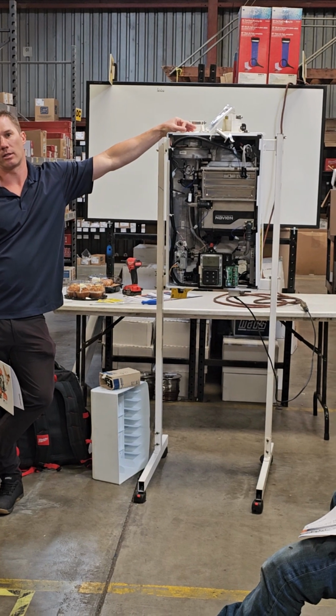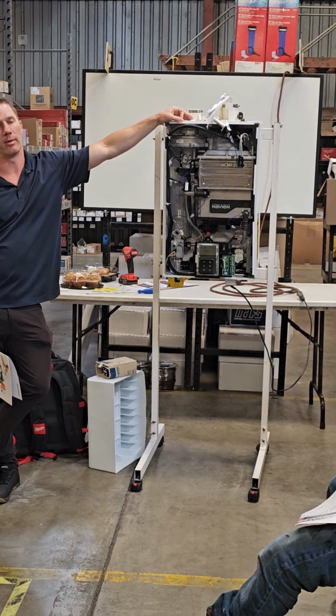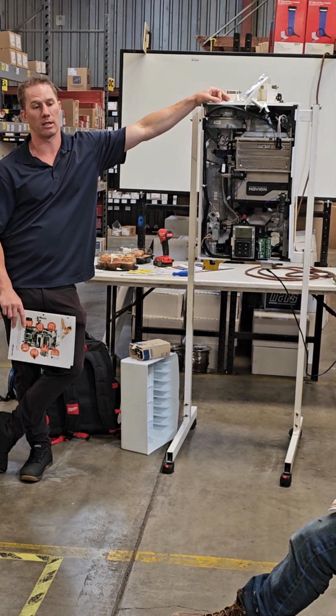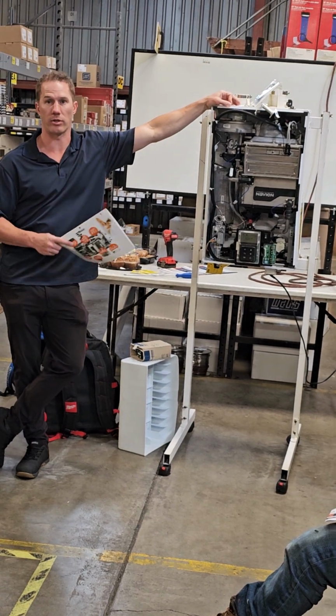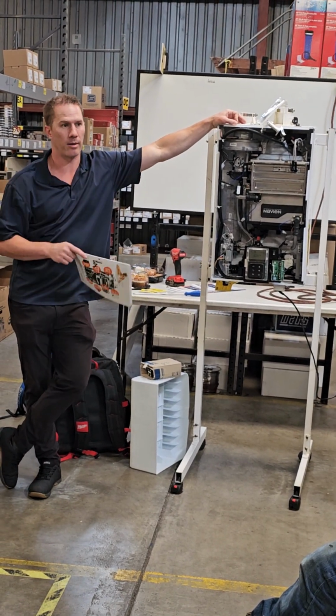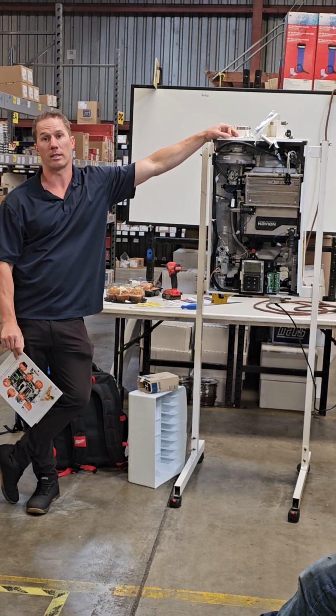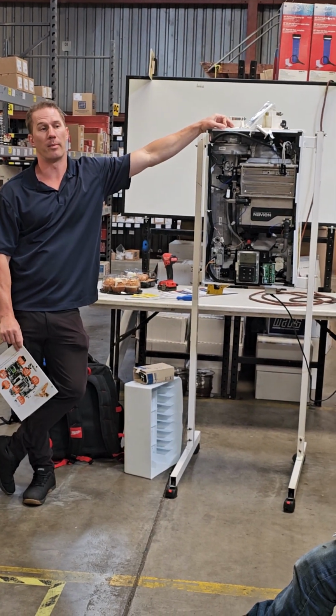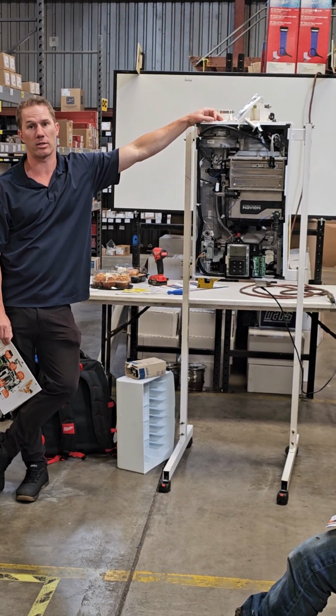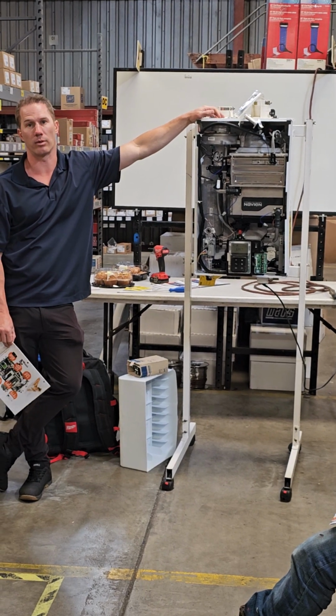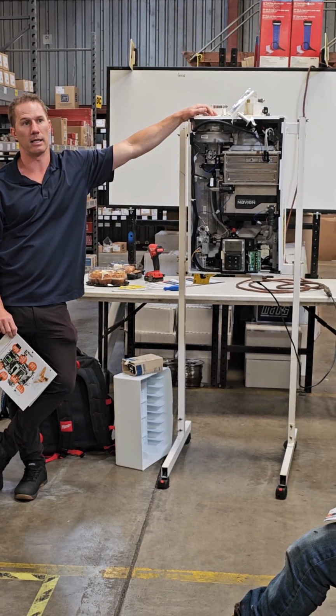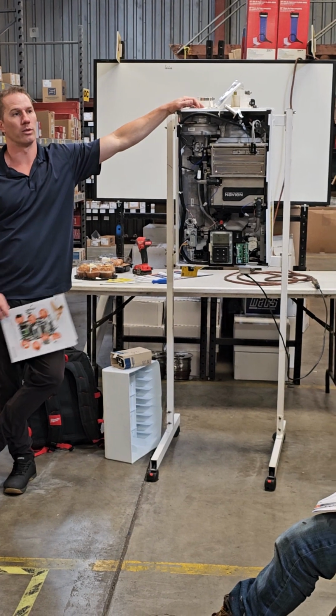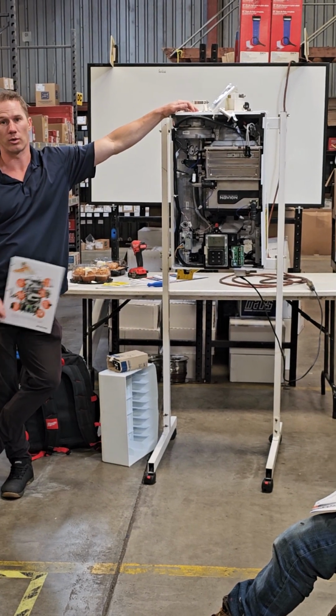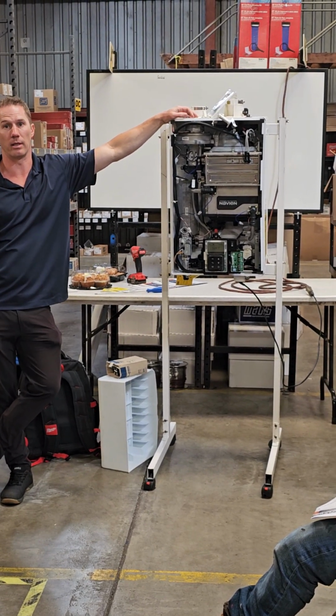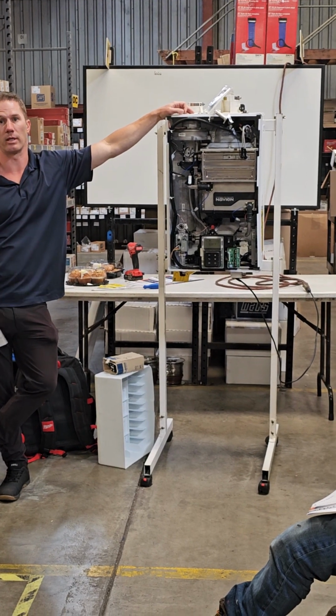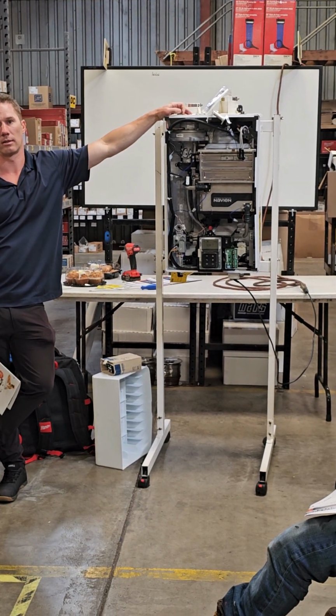With an exterior circulator pump, it only lowers the warranty if it's continuous circulation that never shuts off. Does it have to be on a timer, or can it flow on a switch? On a timer, yeah. But if you hook up an exterior circulating pump, it doesn't do anything to the warranty, unless it's uncontrolled, meaning the pump is literally pumping 24/7, 7 days a week. Well, a lot of residential pumps are like that, you know.